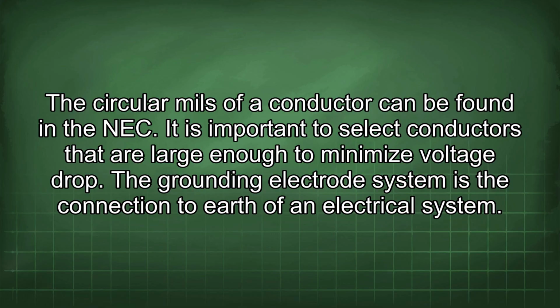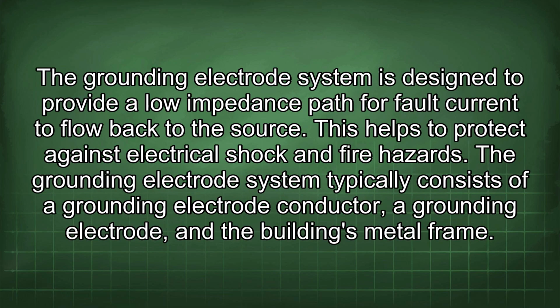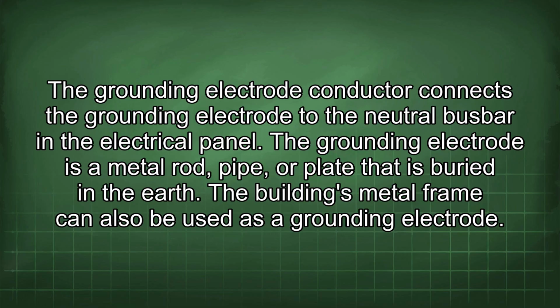The grounding electrode system is the connection to earth of an electrical system. The grounding electrode system is designed to provide a low impedance path for fault current to flow back to the source. This helps to protect against electrical shock and fire hazards. The grounding electrode system typically consists of a grounding electrode conductor, a grounding electrode, and the building's metal frame. The grounding electrode conductor connects the grounding electrode to the neutral busbar in the electrical panel. The grounding electrode is a metal rod, pipe, or plate that is buried in the earth. The building's metal frame can also be used as a grounding electrode.